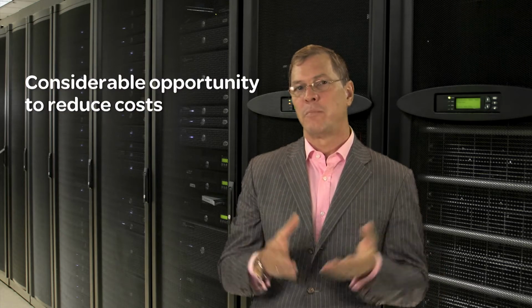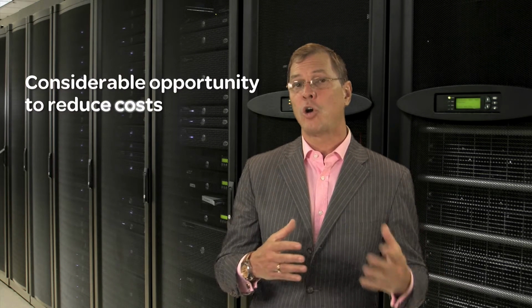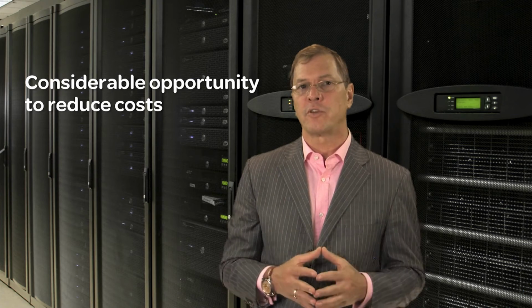Well, the impact that cloud has on the way we deal with redundancy gives us a tremendous opportunity to save considerable cost in the design of the physical infrastructure of a data center. And so we can drill in and understand in more detail a specific example of how this might work. Consider the servers that we typically deploy, which today have 2 power cords. The IT device, or server, or whatever it is, is supposed to be able to operate without interruption from either cord, even if one fails.